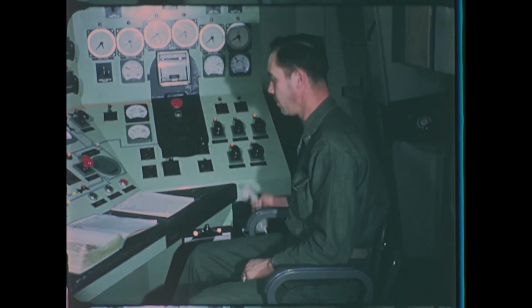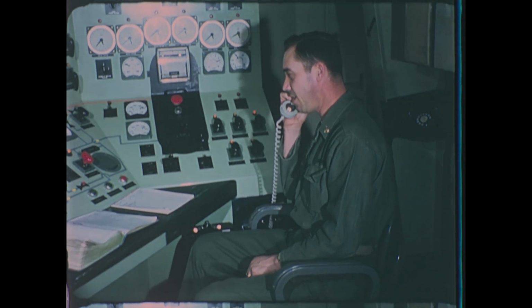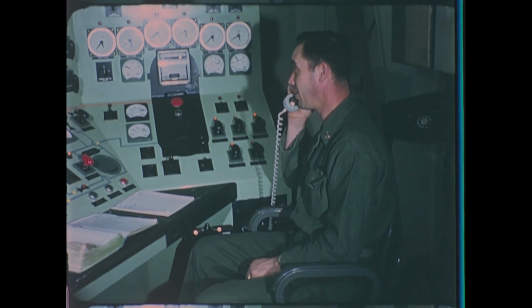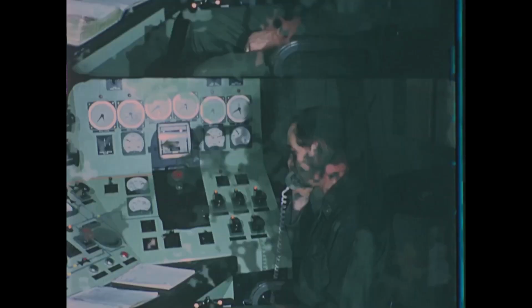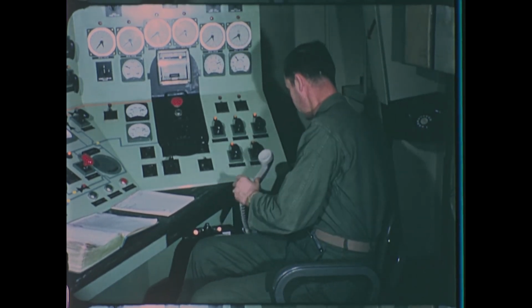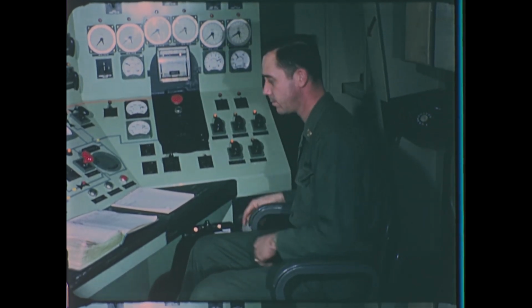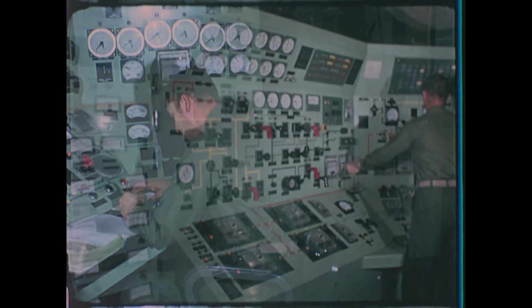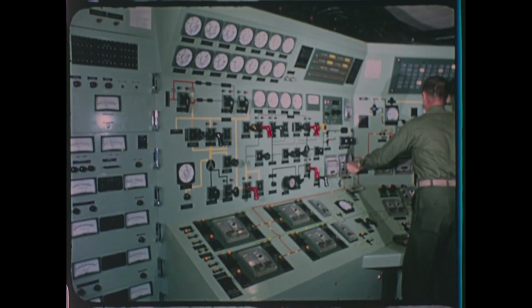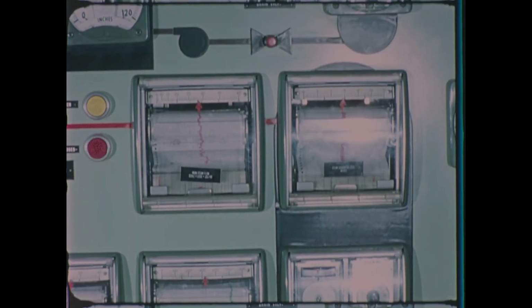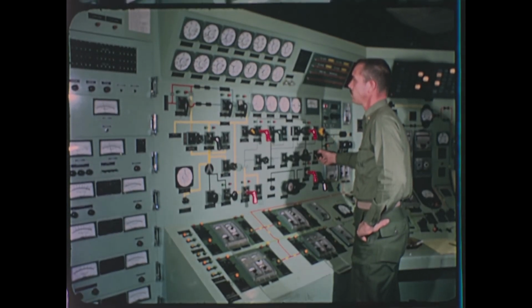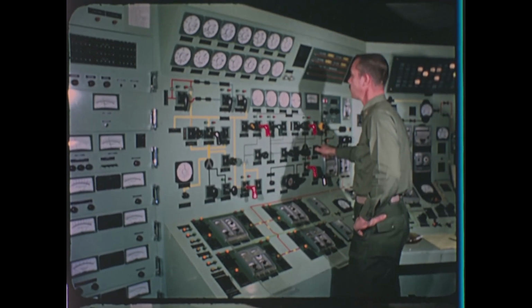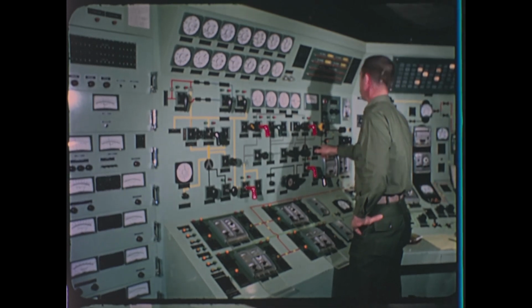After each 2,500 hours of operation, the plant is shut down for testing. When shutting down for this, or for any other maintenance, inform the base electric shop so they can start base diesel generators and assume the base load. Reduce the plant load. Start the plant emergency diesel and assume the plant load.